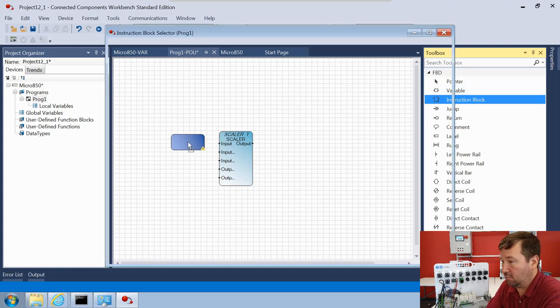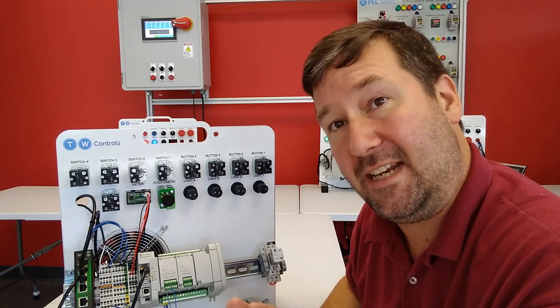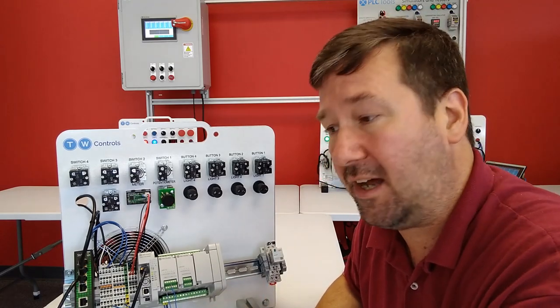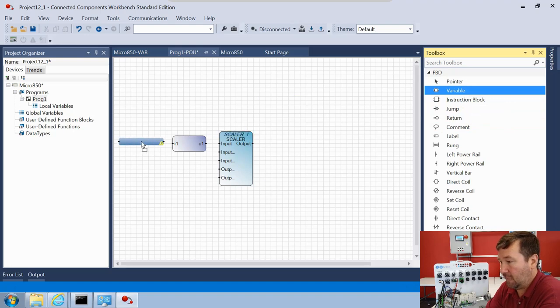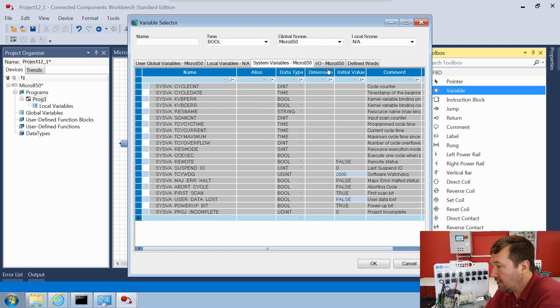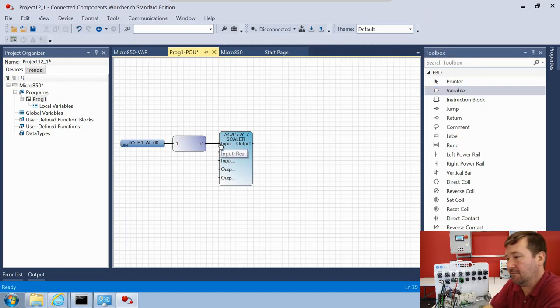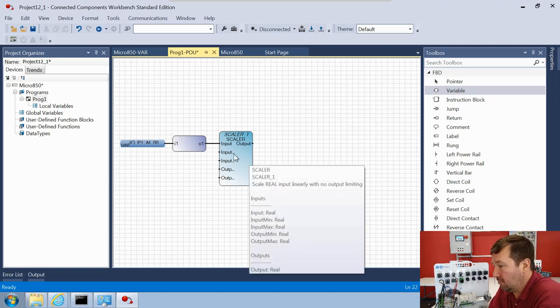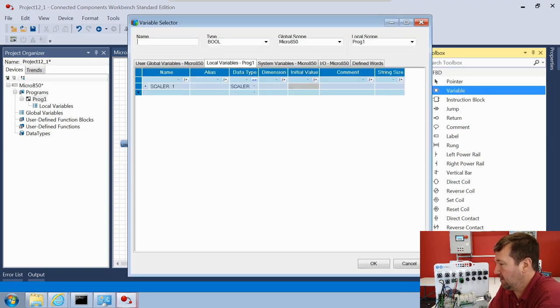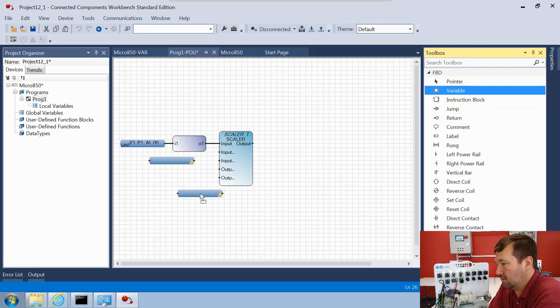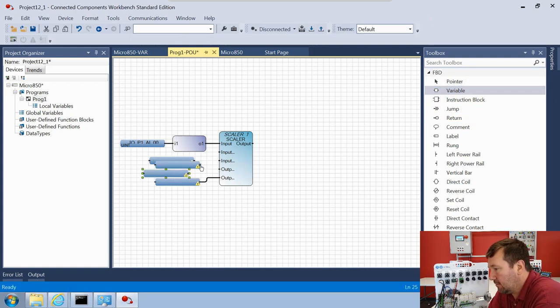Grab another instruction block and type 'ANY' — this brings up the ANY conversion instructions, which can convert almost anything to anything else without pain. Select 'ANY_TO_REAL'. For the input, go to the IO tab and select Analog Input Zero, then drag it to the input pin. That handles the conversion. Now drag down variables for the input minimum, input maximum, output minimum, output maximum, and output — then connect them all to the SCALER block.